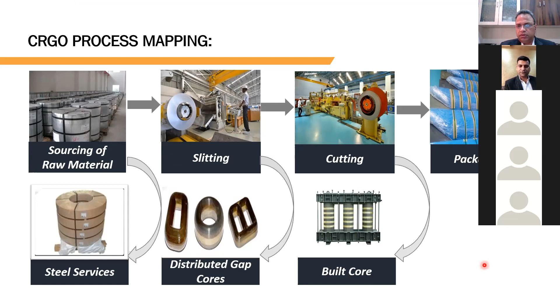Okay. So hope at this level we understand the role of CRGO in transformer performance. Before going for a deep dive into building factor, we just need to differentiate between stacking factor and building factor. Many times we get confused between stacking factor and building factor. So that's why I put a separate slide where I can emphasize the difference between stacking factor and building factor. Stacking factor, as the name suggests, is a stack factor.